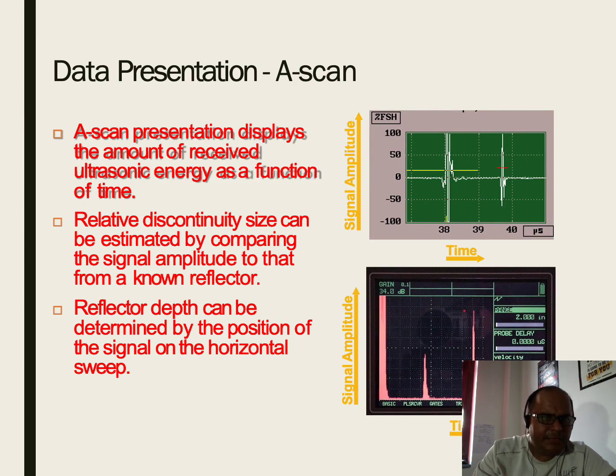A scan is a presentation that displays the amount of received ultrasonic energy as a function of time. Relative discontinuity size can be estimated by comparing the signal amplitude to that from a known reflector. Reflector depth can be determined by the position of the signal on a horizontal sweep.